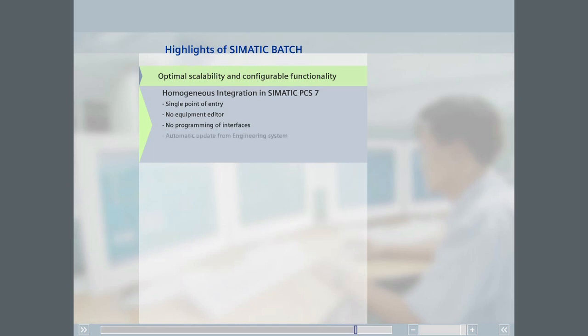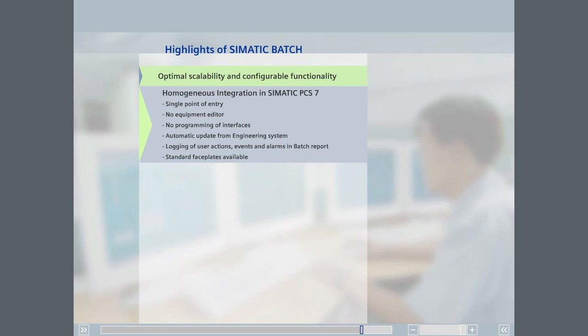Modifications in the engineering system can be adopted with an update function in SIMATIC Batch during operation. Operator inputs and messages or alarms are automatically logged in the batch reports. Batch unit and phase faceplates are available as standard on the OS. SIMATIC Batch supports the formulation of equipment-independent recipes.